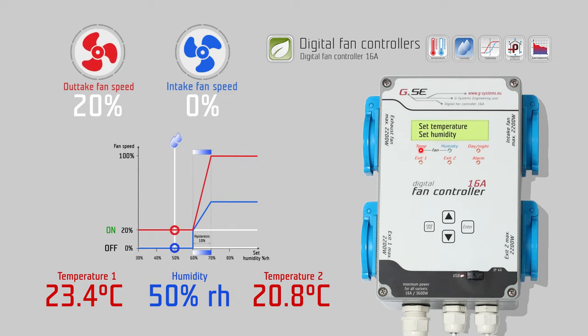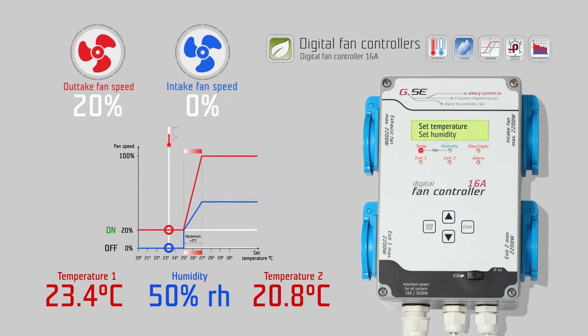Like set temperature, set humidity has changeable values. Repeat the same procedure. In submenu Set Fan Settings, scroll down, select Fan Settings and press Enter. The minimum speed setting limits the exhaust fan. When you press Enter, the value starts flashing. Pressing the down button will change the fan speed from 20% to 0%. The exhaust fan will stop working when the measured temperature or humidity are below their set values.